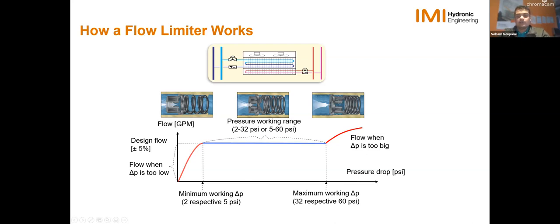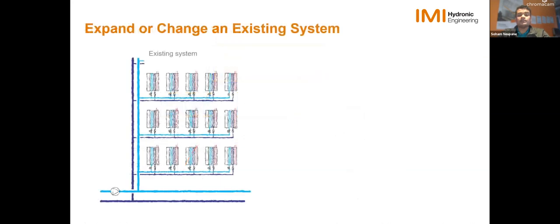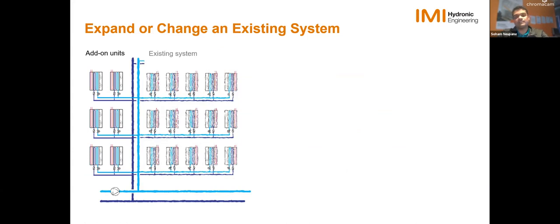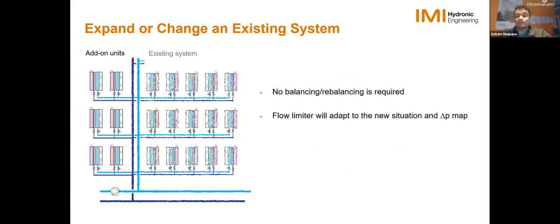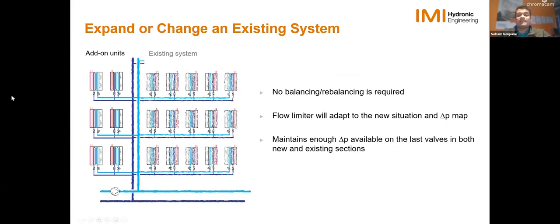So with this solution, the biggest benefit we see is in retrofit projects, like when you have to expand or change an existing system. Say you have a building and you have a new portion that you're going to add to it. With automatic balancing, first of all, you do not need to balance. They self-balance and make sure that you have the water flow everywhere, so it adapts to your differential pressure in the system. So there's no need to rebalance. And whenever you make that addition, you do not really need to worry about what happened to your existing part, because it's not going to be affected at all, since you're not going to see any interactivity. Okay. And that's the automatic balancing solution basically in a nutshell.